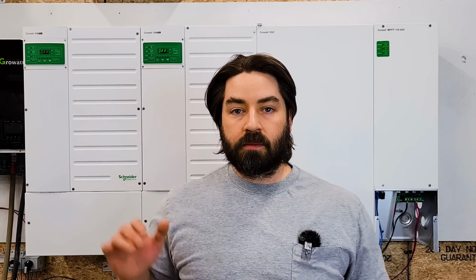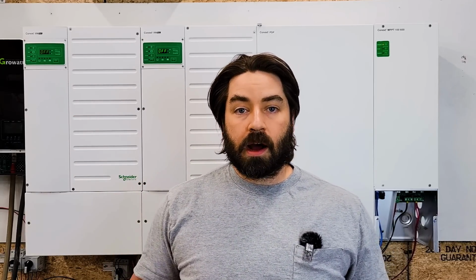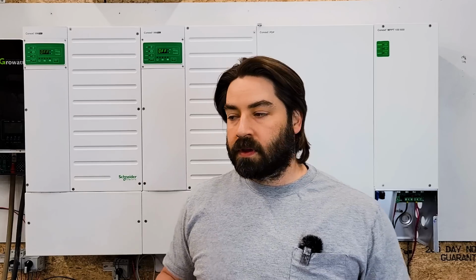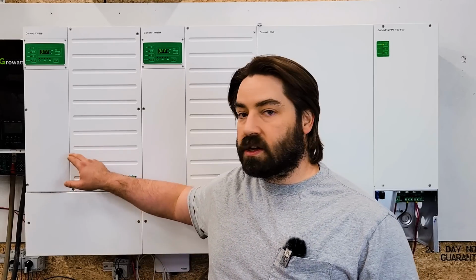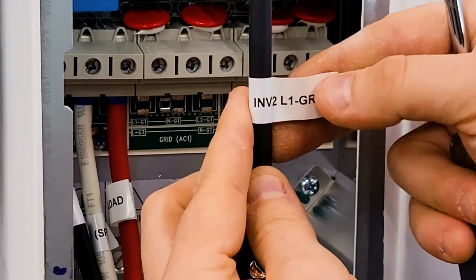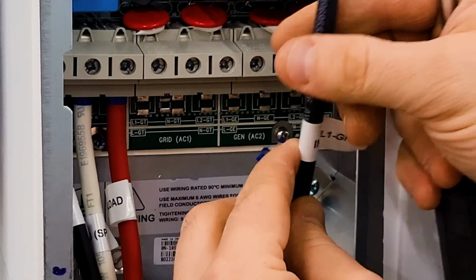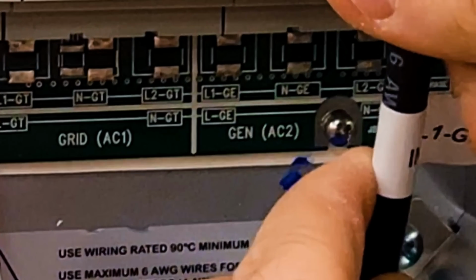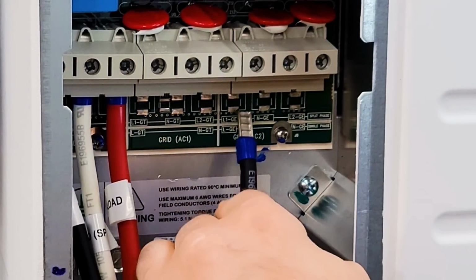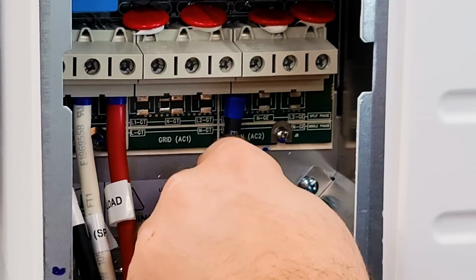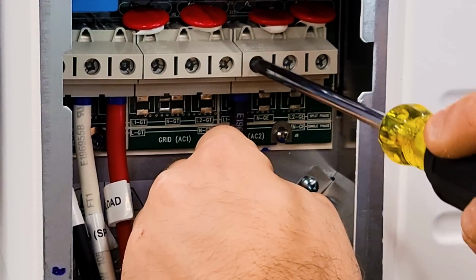Now in my case, I'm running this completely off grid. I'm not connecting the grid to it at all. So I actually ran those to the generator terminals on the inverter, and that's how I'm going to be using them. If I need to run the generator, I can run the generator connected to the inverters, or I can bypass it as well.